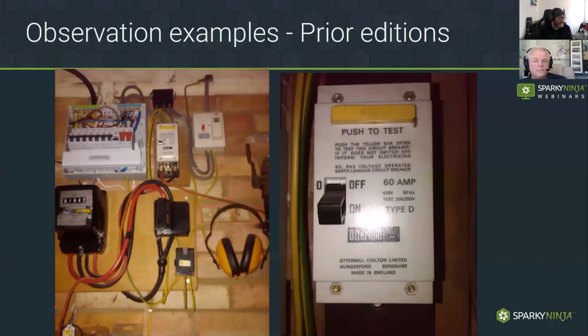I believe the Part P guidance says just leave it as is, but we should install further RCD protection if they're in position. With this example, the electrician thought it was an RCD and replaced the board without installing RCDs, because he assumed the VOELCB was an RCD since it had a big test button on it. So a lack of understanding of prior devices and regulations created this situation.